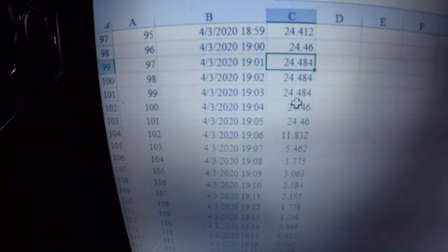And the next one is 25.0 minus 24.5, so it's going to be 0.5 degrees. And if I just continue on down, I'm seeing 0.4, 0.4, 0.3, and 0.3. So I wrote those right in here next to it. Okay, in order to get a grade A, we have to be within 0.5 degrees. Those all are, so basically we get a grade A on all of our high temperature readings.